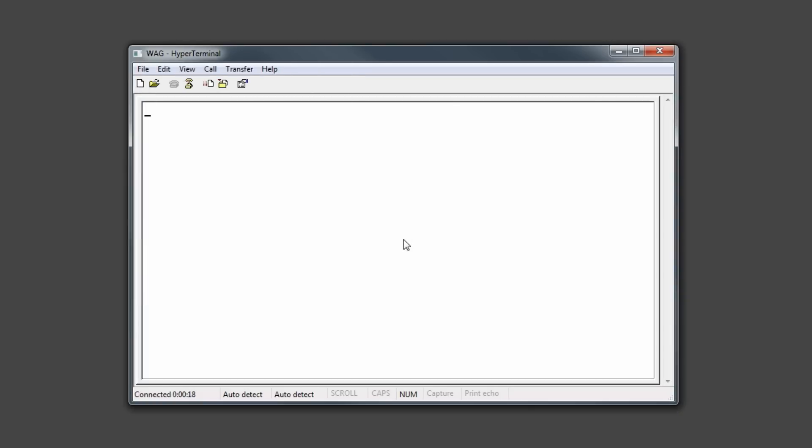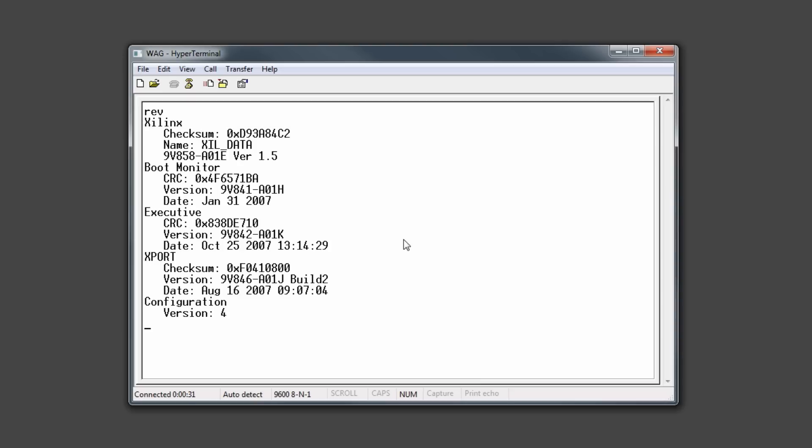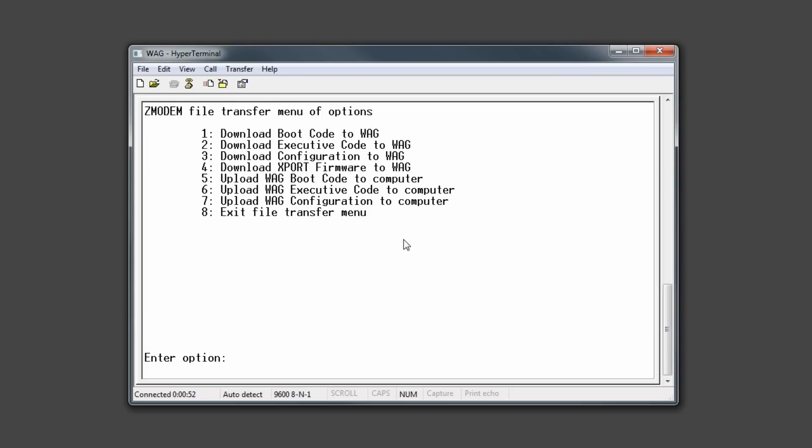The first thing you'll want to do once hyperterminal is connected is check the software revisions currently in the WAG unit. To do so, type REV and press enter. The versions will appear on the screen. Check them against the RailFusion configuration documentation. Generally, the software is already up to date and the only thing you'll need to update is the configuration file. However, if you do need to change any one of the software versions, use the X file command and follow the prompts for downloading software.